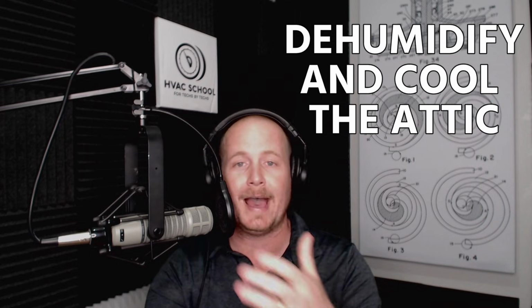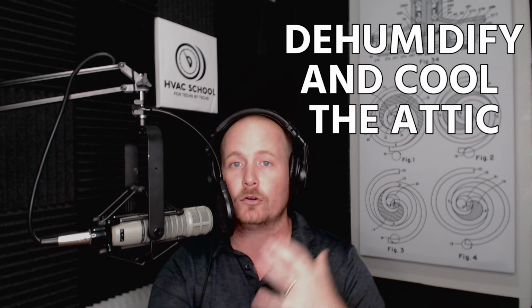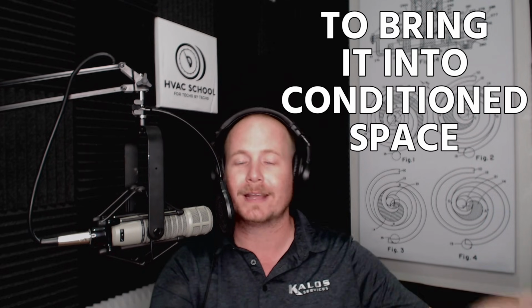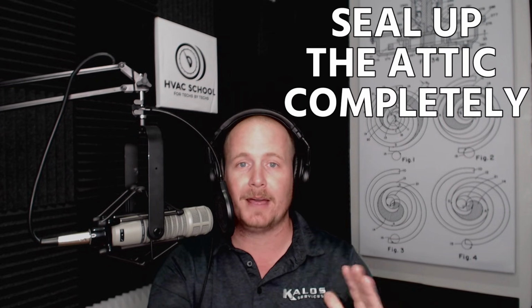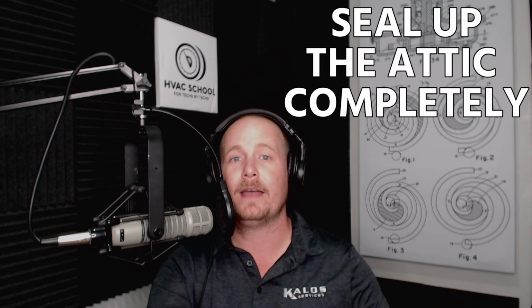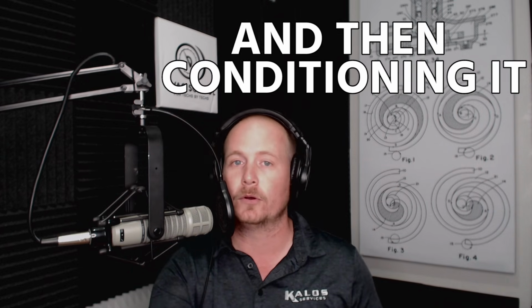That's where we recently used an SD12 from Ultra-Aire in a high performance install that we did, and we used that in order to dehumidify and cool the attic slightly in order to bring it into the conditioned space. And that dealt with that problem that you saw in that video from Jesse, where all the ducts were sweating. By sealing up that attic completely, doing it properly, and then conditioning it, now that whole problem went away and the relative humidity in the attic came down, and also the relative humidity in the space came down.